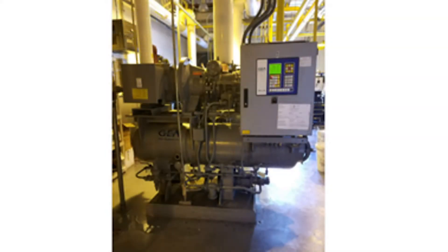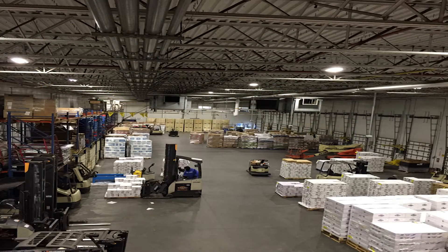This was a cold storage facility with global operations. The particular warehouse we were working with was in the Northeast part of the USA, the greater New York City area. It was a centralized refrigeration system designed and sized for R-22 direct expansion. It had three GEA screw compressors operating at both medium temperatures — roughly plus 20°F — and low temperatures as low as minus 20°F. It was a pretty typical setup for a direct expansion R-22 system.